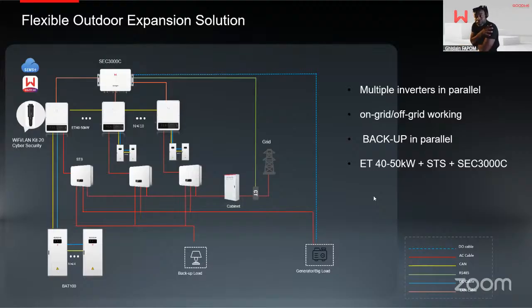We have an outdoor solution, for example, which will use the SEC 3000C. We use only the ET 40 and 50, up to 10. So this is a 0.5 megawatt solution. Each ET has to be connected to its STS box. The STS box can be parallel, so that means the backup can be parallel here. And each inverter can have up to 4 BAT 100, 400 kilowatt hours, so basically 500 kilowatt hours.